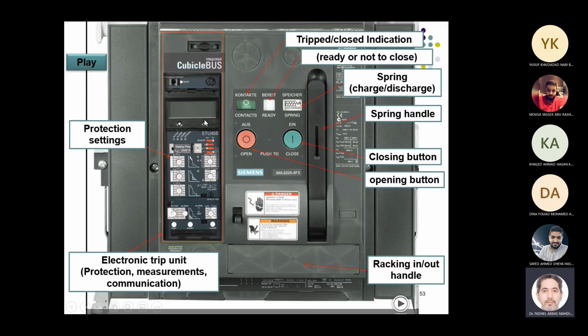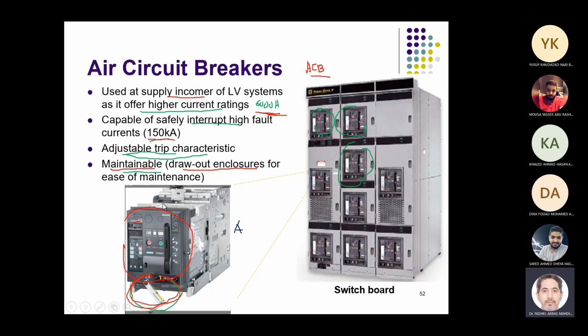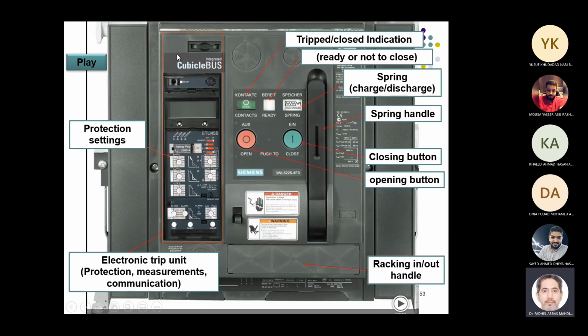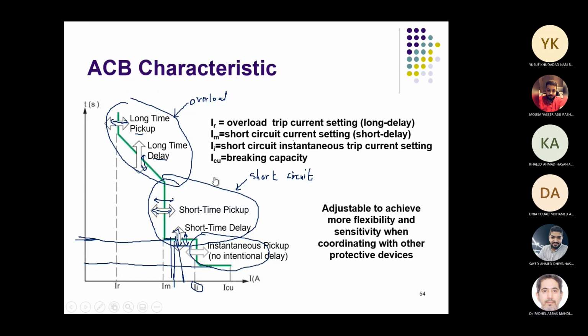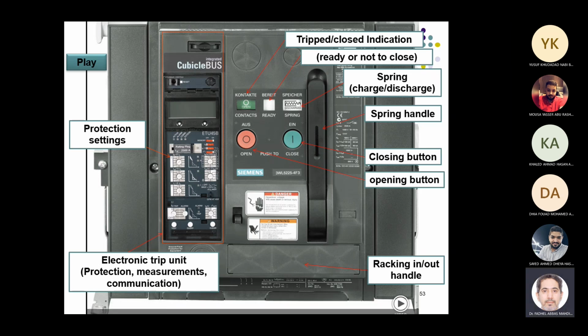This is an illustration, and now we are talking about the low voltage breakers. Okay, so this is an air circuit breaker, which looks like this, and this part is changeable. I can change the unit. This is the trip unit now. This looks like the brain, the relay, which replaced the relay. In here you have the settings for the protection, settings for the overcurrent. This is now electronics, whereas in MCCBs and MCBs the protection elements are electromechanical, while here it's electronic, where you sense the currents and voltages electronically and compare them with the setting.